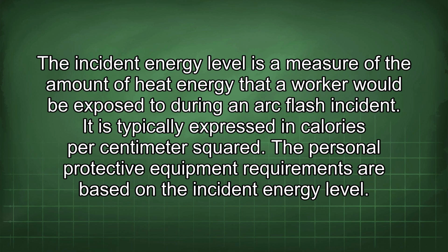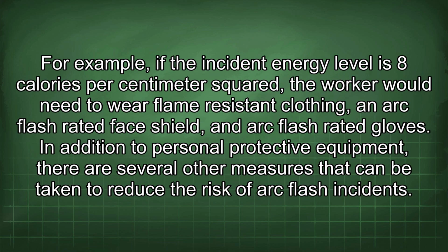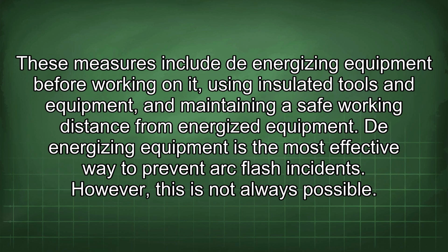The personal protective equipment requirements are based on the incident energy level. For example, if the incident energy level is 8 calories per centimeter squared, the worker would need to wear flame-resistant clothing, an arc flash-rated face shield, and arc flash-rated gloves. In addition to personal protective equipment, there are several other measures that can be taken to reduce the risk of arc flash incidents. These measures include de-energizing equipment before working on it, using insulated tools and equipment, and maintaining a safe working distance from energized equipment.